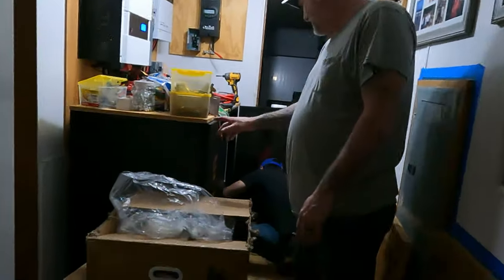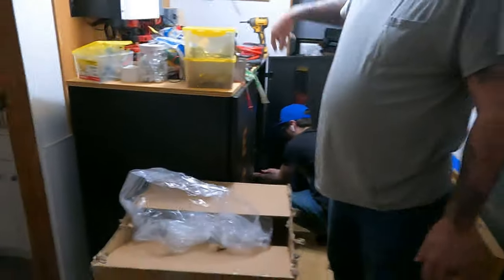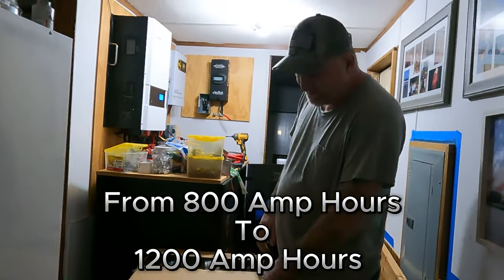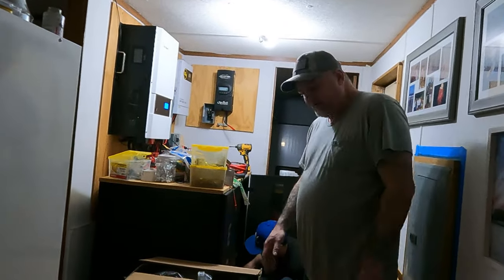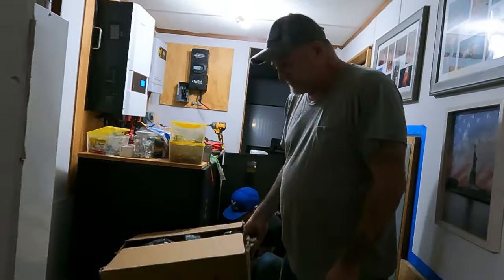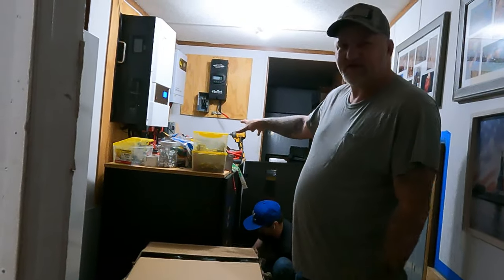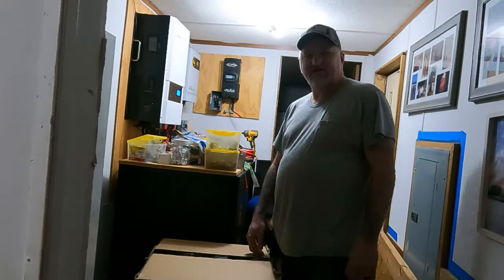He's putting one in the bottom cabinet now and I'll make the jumper wires. So far this ought to be a pretty dramatic change in the battery system. We've had about 12 batteries — that's over half a ton right here in these two cabinets, 1,200 pounds. These batteries are 100 pounds apiece in the boxes and there's 12 of them, so that's 1,200 pounds — over half a ton of batteries sitting right here on the floor. Anyway, we'll get these in and we'll be back.